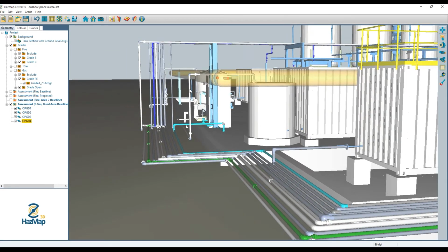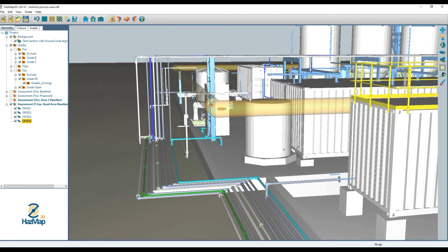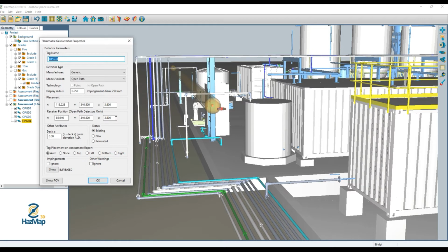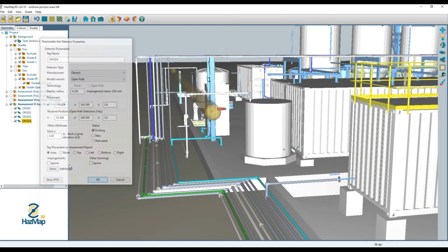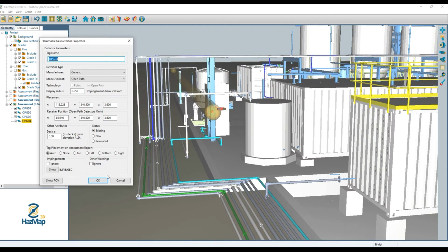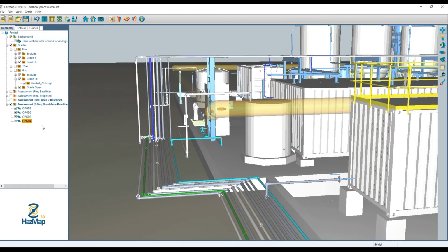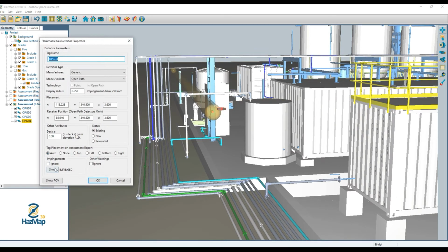And what I'm finding is I have those pipes up here. I have this one blocking, but I don't want to move up because I have this one over here. So since I don't want these to be interfering with each other and because I don't want the pipes to be interfering, since I started out at 2.5, I'm just going to try and reduce this to about 2.3 meters above the deck, which should still be acceptable. I'm still getting an impingement warning, so what does it say? Okay, it's still saying the post is getting me.